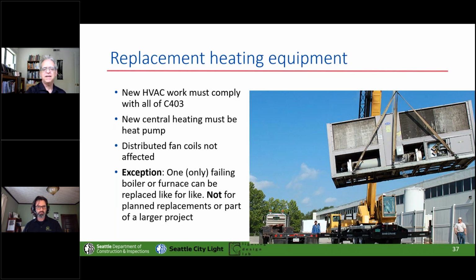If we're replacing heating stuff, anything new you do has to comply with the whole HVAC system. If it's a central system, it has to be a heat pump. Now, if you've got one of those many Seattle office towers with VAV reheat, you know, the electric reheat on, and you're replacing individual fan coil units around the building, and it's not a substantial alteration project, then this doesn't kick in.